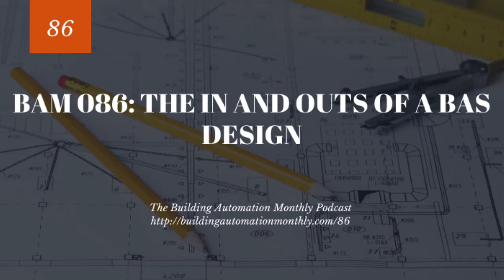And this is the typical structure. This may vary if you're outside the United States. But part 2 is going to be products, and it's going to say, well, this is the building controller, this is what it's going to be capable of, this is the field controller, this is the field trunk. These are just the capabilities of the individual products and devices. And the sensors, they're going to be of this type, and they're going to have this kind of output, this kind of tolerance, etc. And then execution is how things are going to be executed, how you're going to go and do the work, how the work's going to be coordinated, all these kind of things.